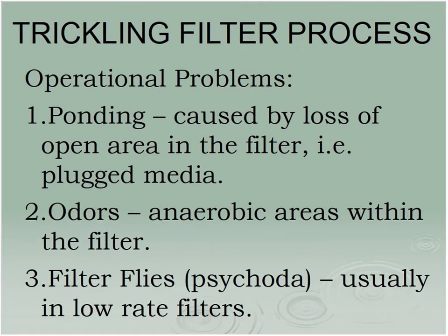So we talk about operational problems. Fall is a particularly tough time of year for trickling filters when all the leaves are dumping out, depending on where they're located. You've got to make sure the top of these beds are clear. Ponding refers to just that. You take a look at the top of your filter and you've got standing water. What that means is your media below that is plugged for one reason or another. And if no water is flowing through there, then likely it's going to dry out, it's going to go anaerobic, it's going to smell, and you're going to get calls from the neighbors. So you have to deal with that.